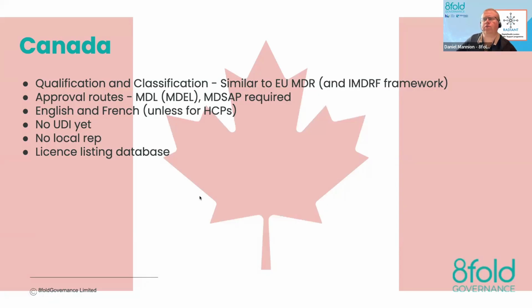Canada, so their regulator is called Health Canada. Their qualification and classification criteria are very similar to the EU MDR and to the IMDRF framework. There is an MDL, which is a medical device license, and a medical device establishment license. So you get a license for your product, and you get as part of that a license for you as a manufacturer. You must have MDSAP certification to sell any medical device in Canada.